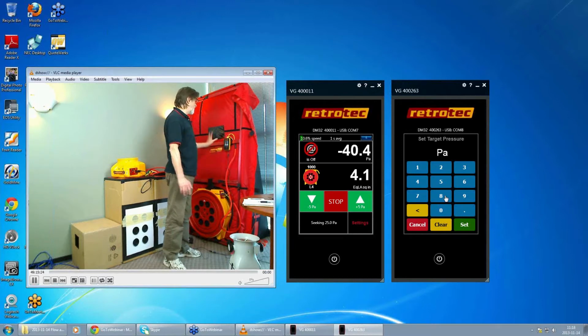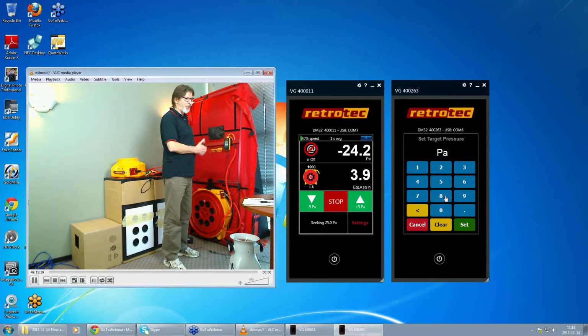Let's give that a chance to settle itself out. And it looks like it's settled out at 3.8, 3.9. So originally we got 20, minus 3 or 4 is 16, which is exactly the hole that we had in there. So this is a really fast way to check your blower door.